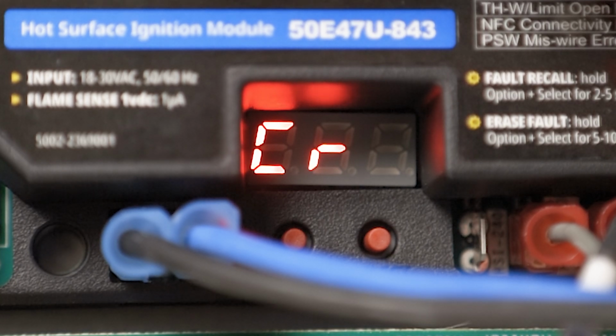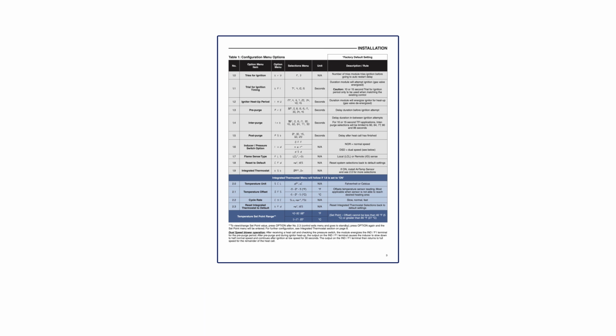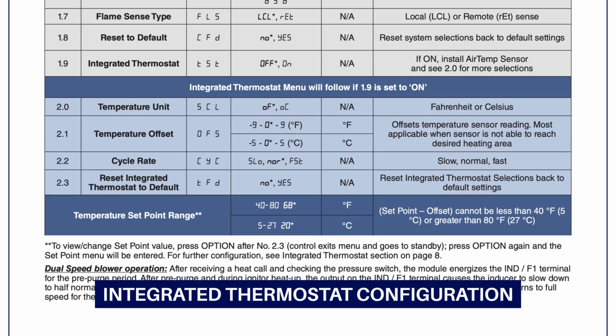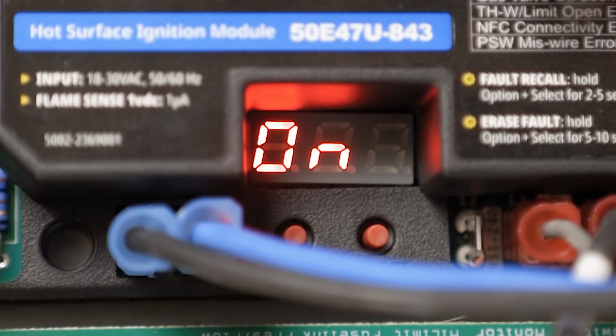To enter the configuration mode, hold the Option button for 3 seconds while simultaneously supplying 24 volt to THW. Table 1 on page 3 of the installation instructions shows configuration options. Included at the bottom of the table is the configuration options when utilizing the integrated thermostat. For this application, the control will need to be configured by matching the settings of the existing module.